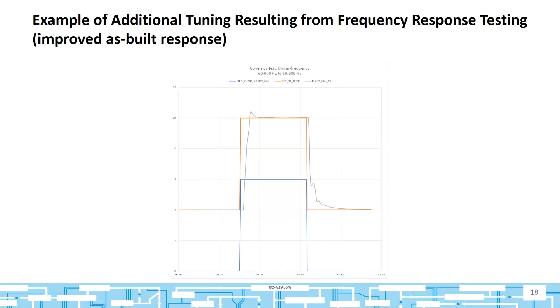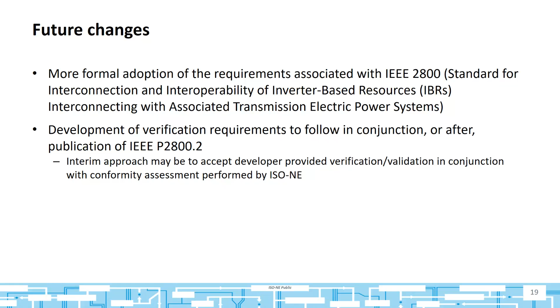So we're going to continue, obviously, to do the commissioning, adoption, and testing requirements that I described, but advance them by adopting more formally the full set of requirements of IEEE 2800, where we're specifying actual performance expectations, say in terms of things like response rates, and looking at that they be specifically demonstrated when the resource comes online, either in conjunction with IEEE testing standard P2800.2, or in the interim with developer provided validation while we're waiting for all of those standards to be put in place. And I think that takes me to the end, Alex.